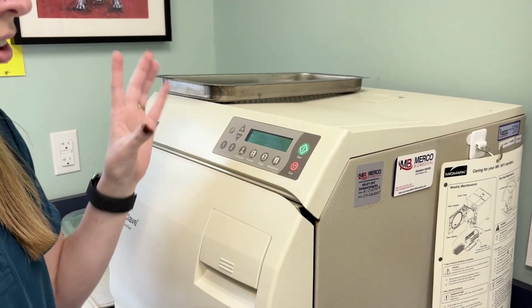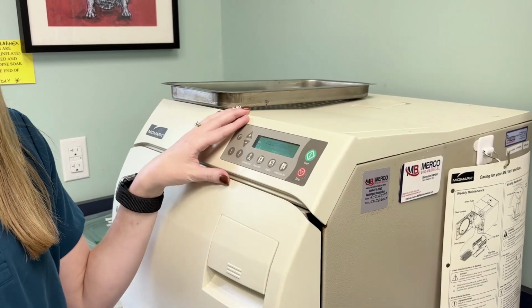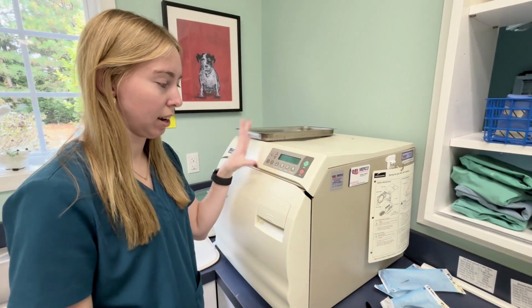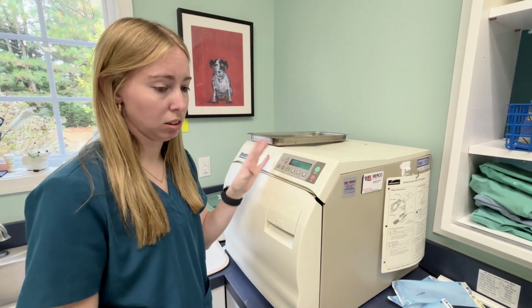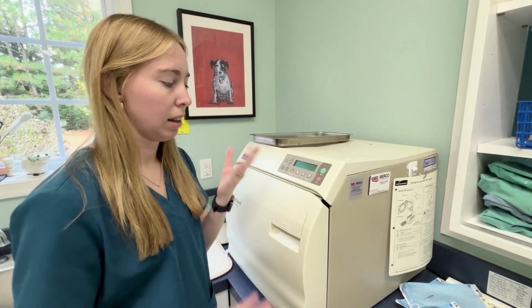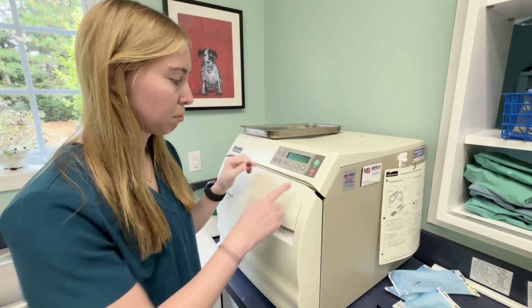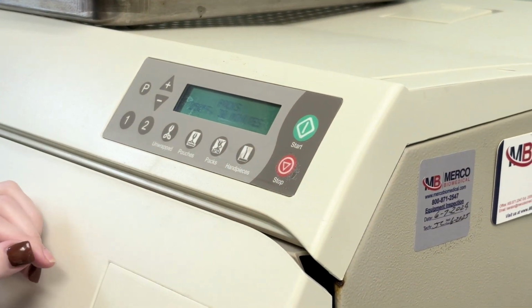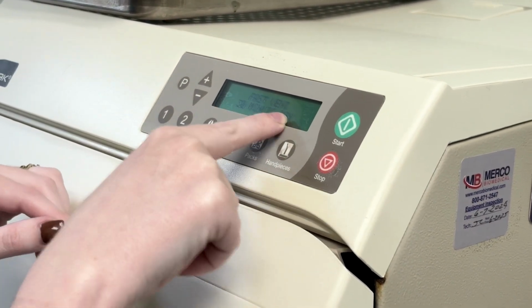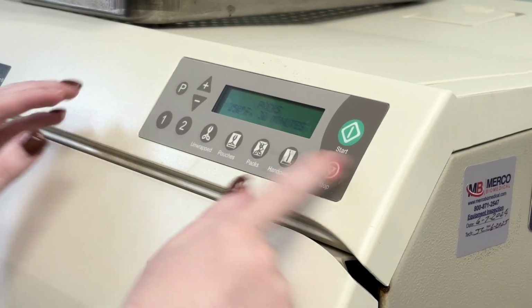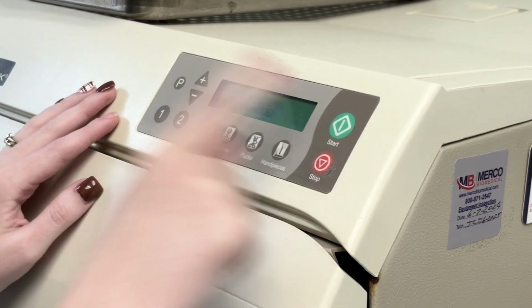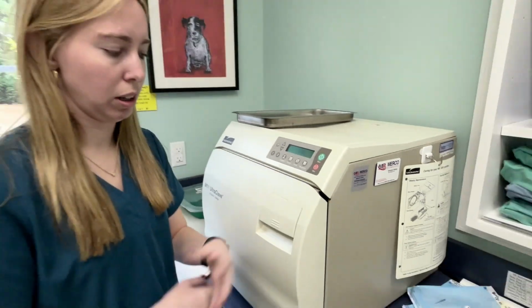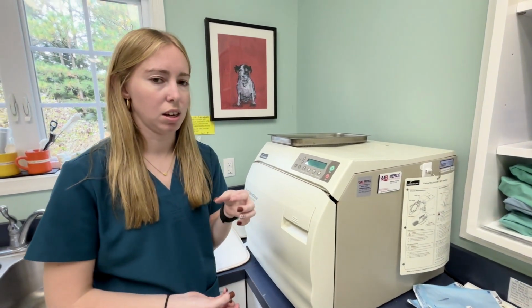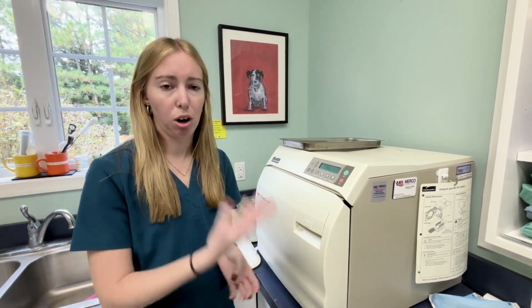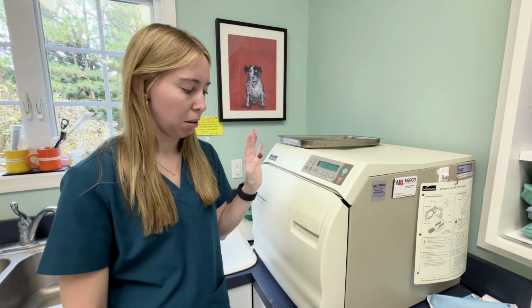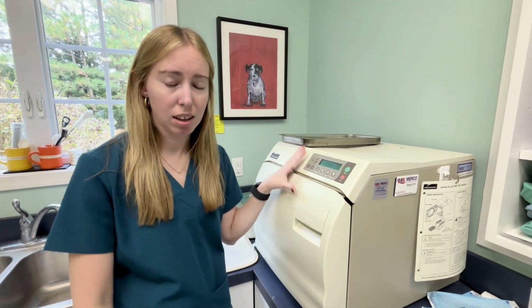Whereas the pouches are at 270 degrees Fahrenheit with 27 psi, and they're only sterilized for 5 minutes because it's easier for the steam to get in there, and then they dry again for 30 minutes. So I am going to pick my pack cycle. It says right here 250, 30-minute dry, and 30-minute sterilization. Then I will press start, and it'll automatically start going. The door will pop open when it's ready to dry, so it'll automatically vent itself.